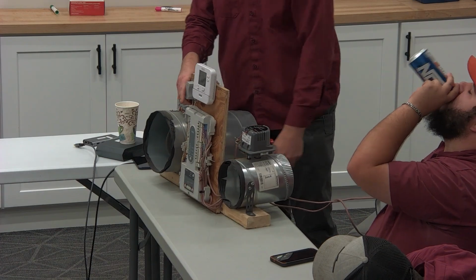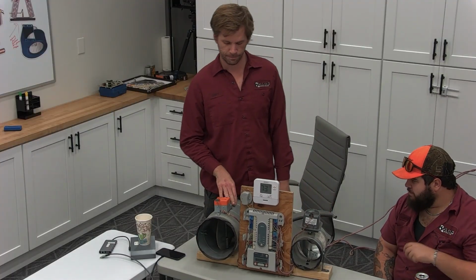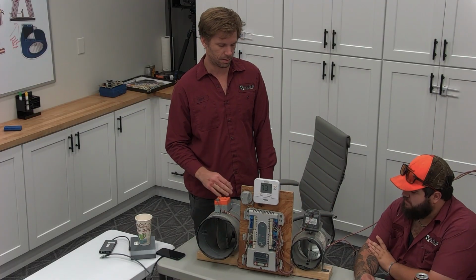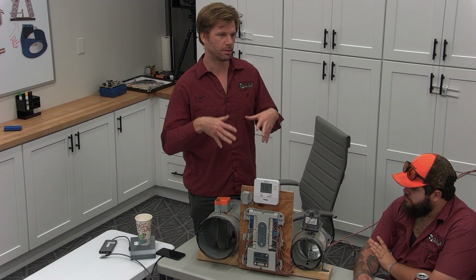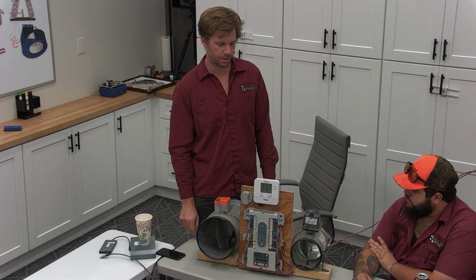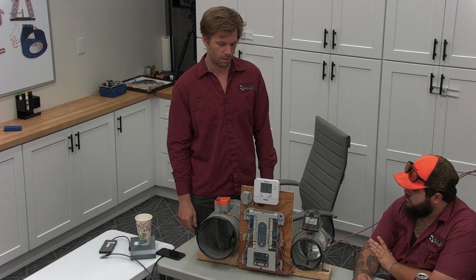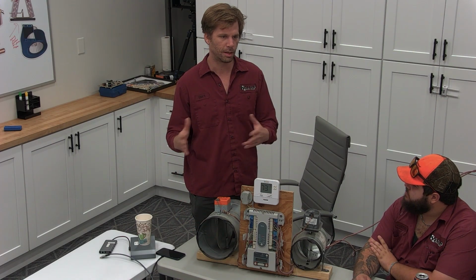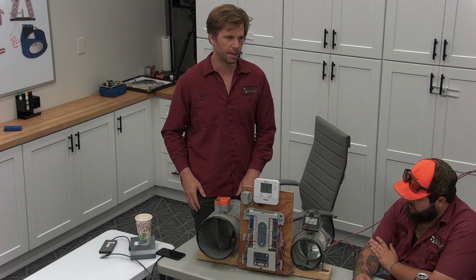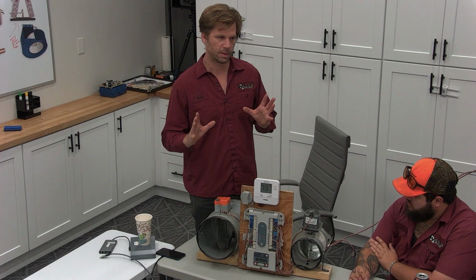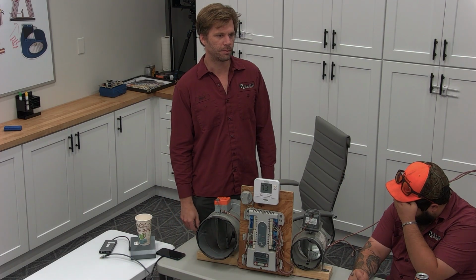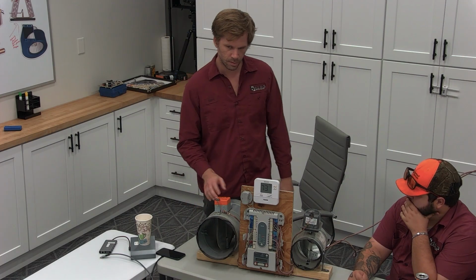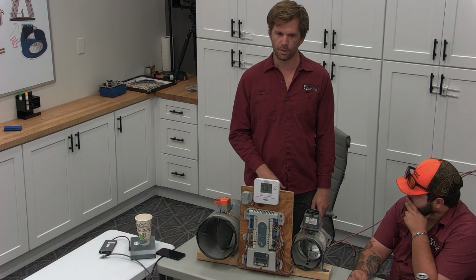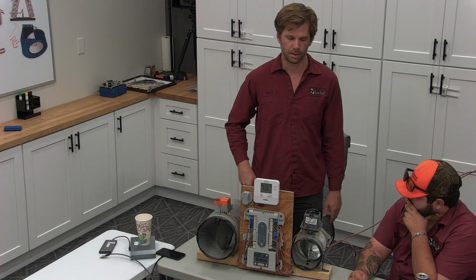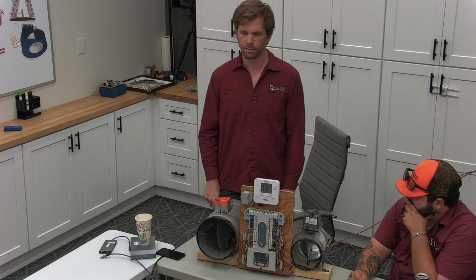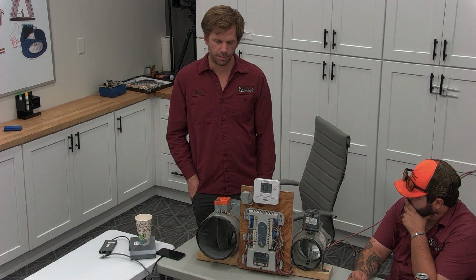So if you had a really small zone and your system, a large system dumping a lot into a small zone, could be a major static pressure issue, an airflow issue. So you could keep the large zone partly open. It never fully shuts all the way. And then your small zone is still going to probably satisfy quick enough before the big zone becomes uncomfortable.